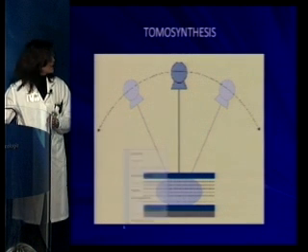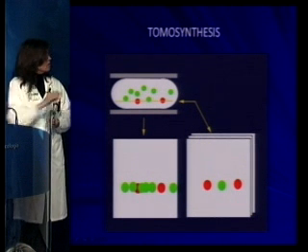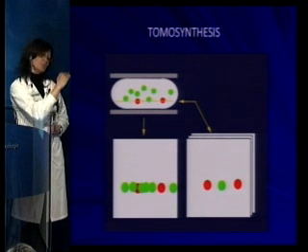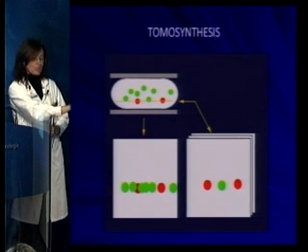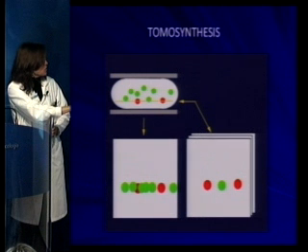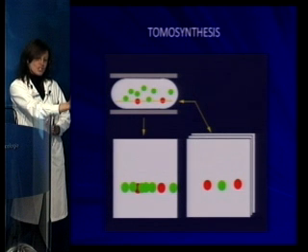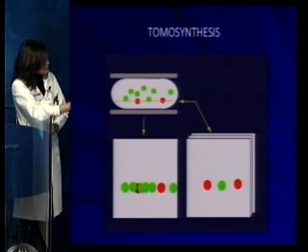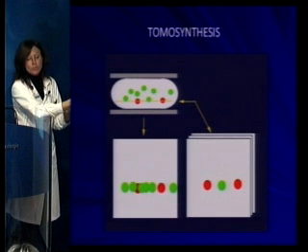With this method, we can eliminate or reduce overlapping images, by removing information from objects that are above or below the layer on which we focalize the acquisition. We obtain many very thin images near to each other, and we can view them individually or in a cinema mode, obtaining images that improve the visualization of single lesions without overlapping.